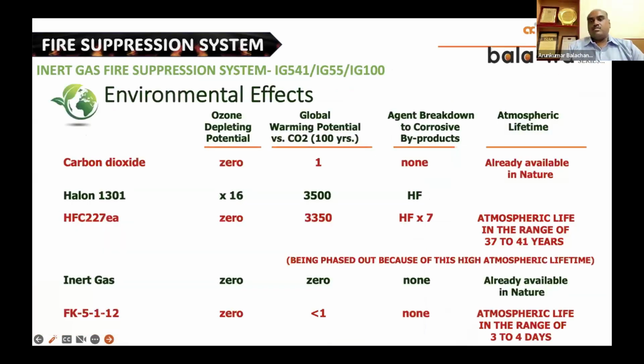Let us come to the environmental effects, because this is much more important for many people nowadays, especially with net zero targets being taken by a lot of companies. As we know, carbon dioxide is not widely used because of its global warming potential, and also it is very harmful for human applications. We have the inert gas, which is zero in ozone depletion and zero in global warming potential. Since the inert system is not a reactive system, it is an oxygen displacement method. There is no breakdown of inerting due to any corrosive byproducts. And for atmospheric lifetime, inert gas is already available in our air, so we are not adding anything new into our atmosphere.